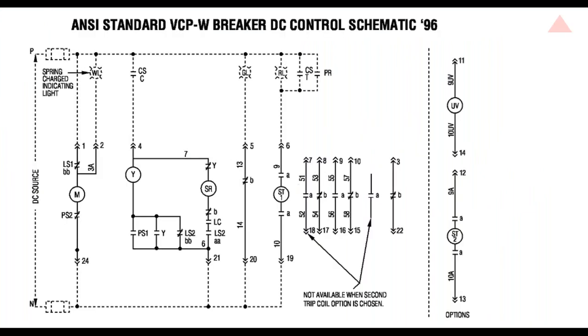A breaker would operate just fine without the Y relay — in other words, you could disconnect it and not know for 40 years, until you needed it. Now let's look at a breaker electrical schematic and see if we can understand how it's doing electrically what we want it to do mechanically. The first circuit on the breaker diagram is usually the motor circuit on the left. We have positive at the top, negative at the bottom, and the customer wiring (shown as a dotted line) comes in through auxiliary stabs in the test or connected position.